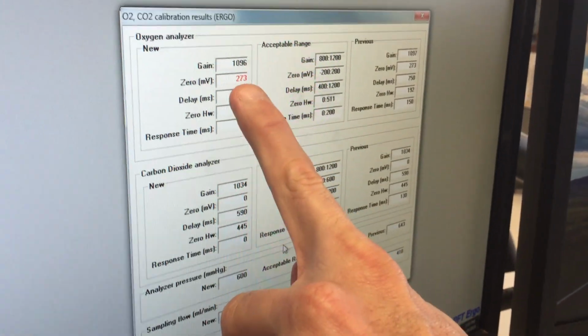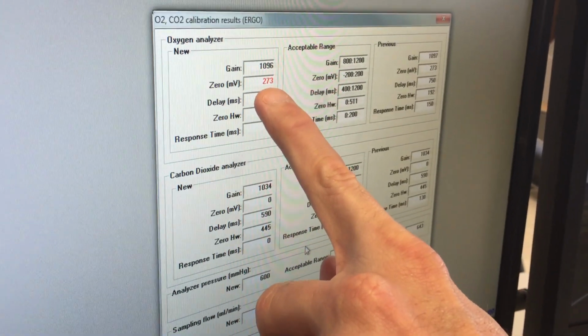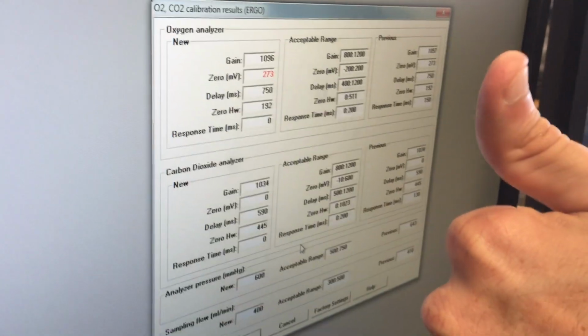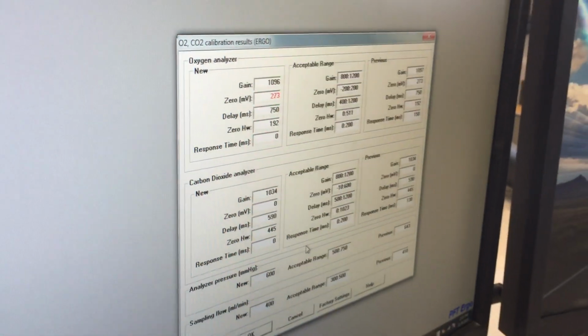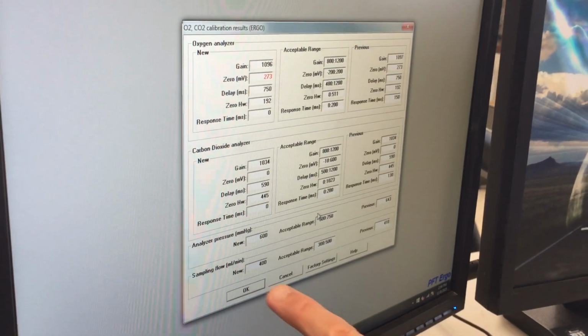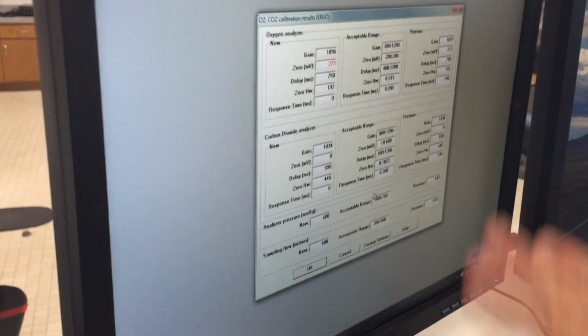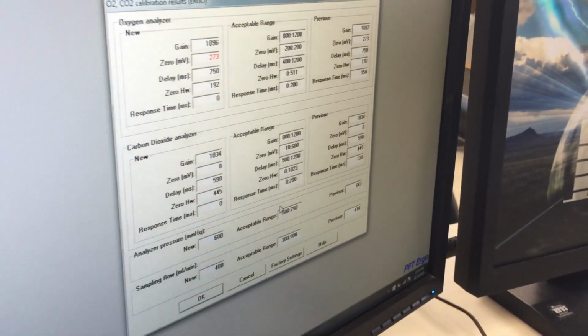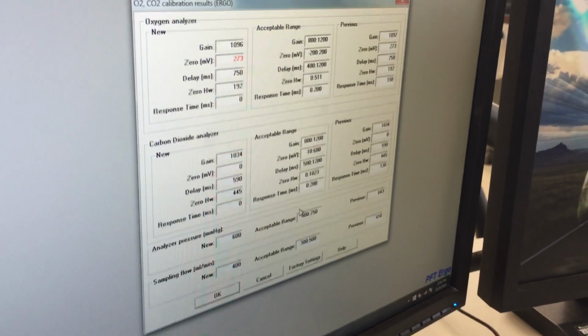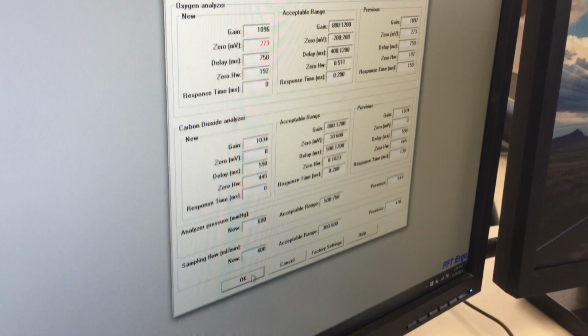You will likely see this number in red. If it says 273 and it's in red, that is okay. If you see all of that and everything else is in black, we hit okay. If for some reason you see a lot of red numbers all over the screen, that means something wasn't calibrated right. You should shut everything down and start again. So here, everything's good. We hit okay.